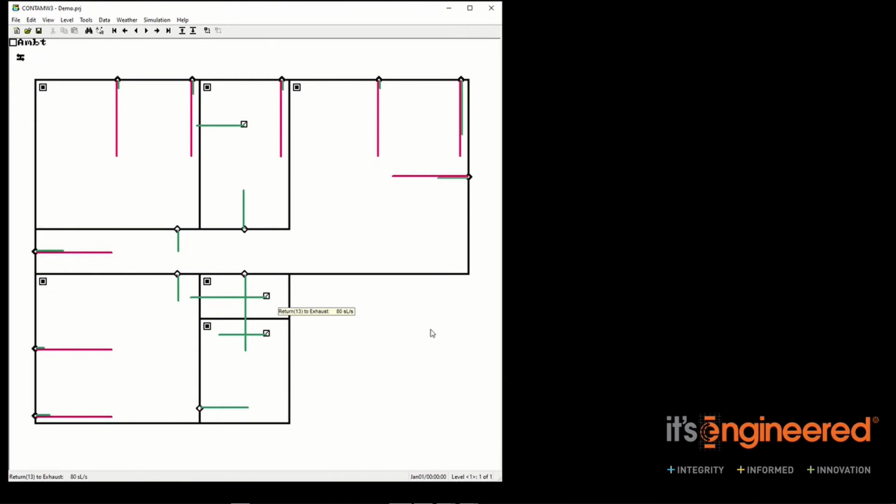Okay, so having a bit of a look around, again we've got some air coming through around the door. We've got the balcony door, we've got air leaking through windows, and we've got air leaking through the facade of the building. Now we can see that the space here is just over 12 pascals below the ambient. So the pressure drop across the facade is just slightly over 12 pascals. But I'm still using some cheap old doors and windows, so let's tighten those up to a newer spec.